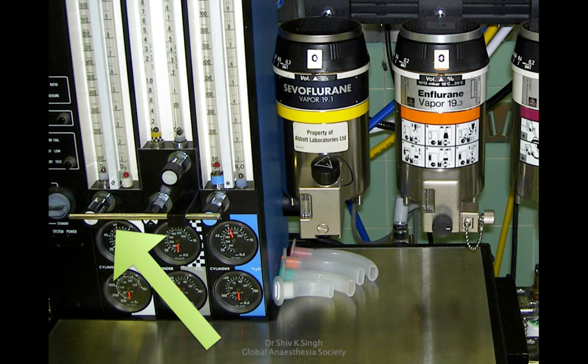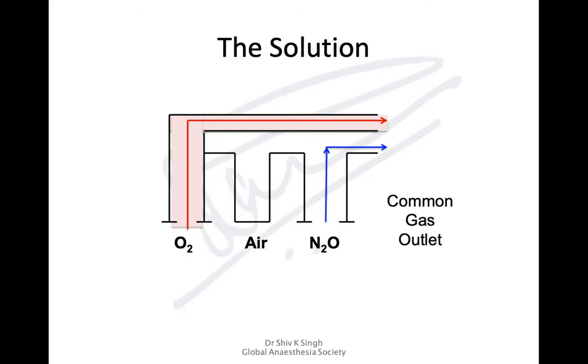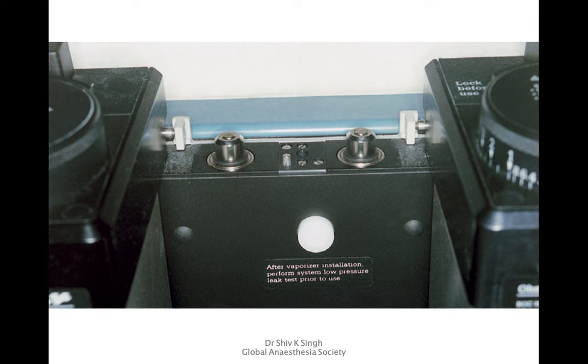The ultimate solution was to deliver oxygen separately and directly to the common gas outlet, independent of air and nitrous oxide. This solves all problems — you don't need to worry about the position of the oxygen flow meter (upstream or downstream), as it connects directly to the common gas outlet.